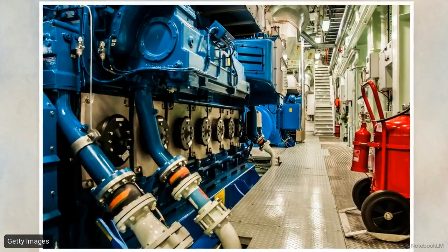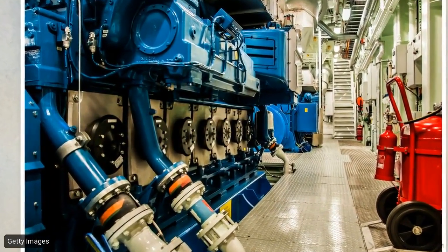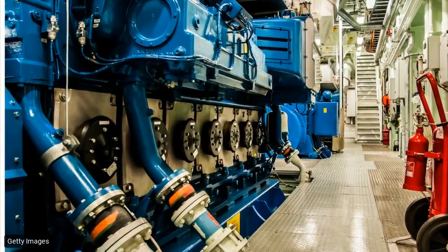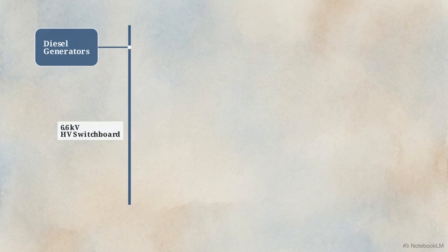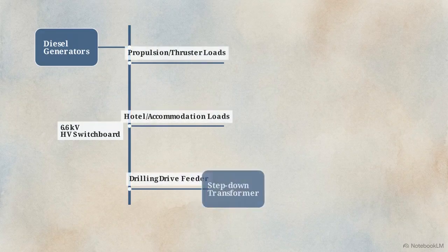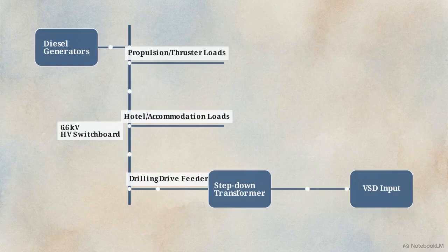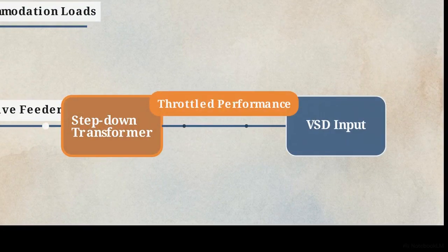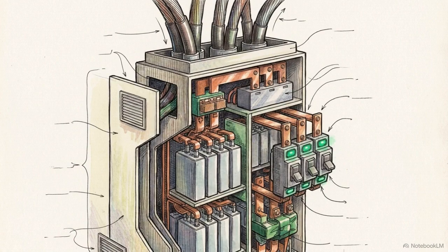The electrical path starts with multiple diesel generator sets running in parallel to ensure redundancy and grid stability. Each alternator produces AC power, typically at 6.6 kilovolts. This feeds the high-voltage switchboard, routing energy to drilling and propulsion loads. From here, power branches into step-down transformers, dropping to a compatible input voltage for the drives. If these transformers are undersized, they throttle the drawworks performance, regardless of how advanced the motor is. The entire path must be sized as a single chain. This distribution chain delivers raw power to the threshold of the variable speed drive, where mechanical control begins.